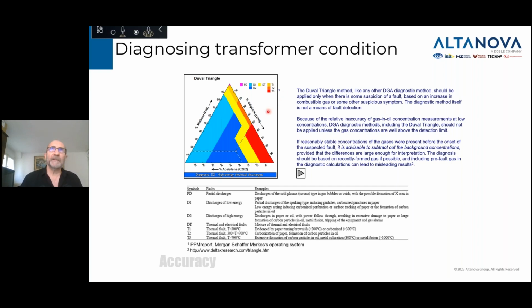Why Duval is very popular around the world is mostly because Duval not only developed a mineral oil triangle years ago, but has continuously improved his triangles and developed new ones. Today, you have a low temperature fault triangle that can tell you if you have stray gassing or carbonization. You also have triangles for silicone, triangles for ester, natural and synthetic, and triangles for OLTC. On top of that, he has developed a pentagon, mostly used if you have not just one specific fault but a conjunction of faults. The pentagon, in conjunction with the Duval triangle, allows you to better pinpoint what the fault is and gives you a much better diagnostic.